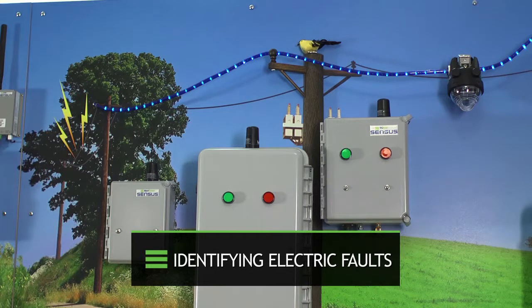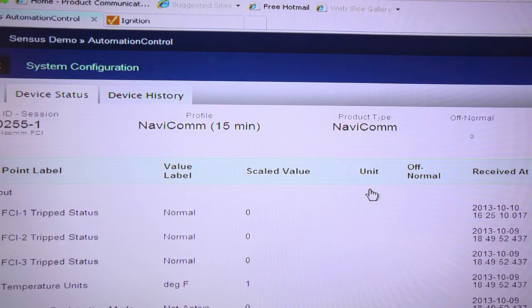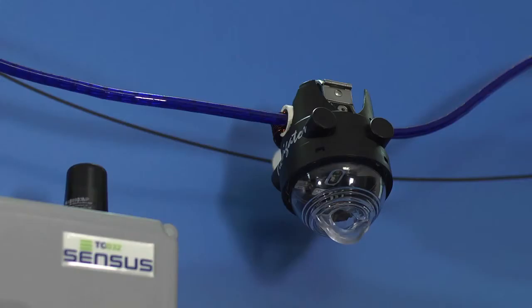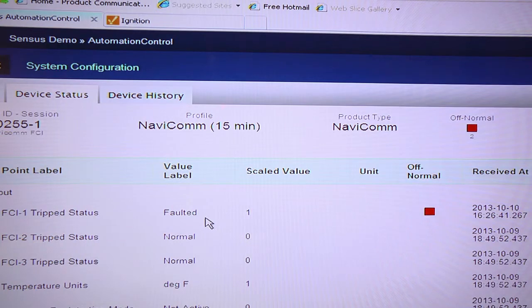Sometimes faults occur on the electric system, like a tree contacting the electric wires. FlexNet technology enables the FCI to talk to the utility quickly to find the location of a fault and dispatch repair crews to the site. I'm on my automation control software, communicating to a NaviComm fault current indicator. FCI number one is in the normal position. Switching over to my Ignition SCADA package, I'm going to simulate a fault on the distribution line. We can see a tree is brushing the line — it's causing a fault. Our fault current indicator is blinking, communicating to the FlexNet system to send that information quickly back to the utility via the automation control software.